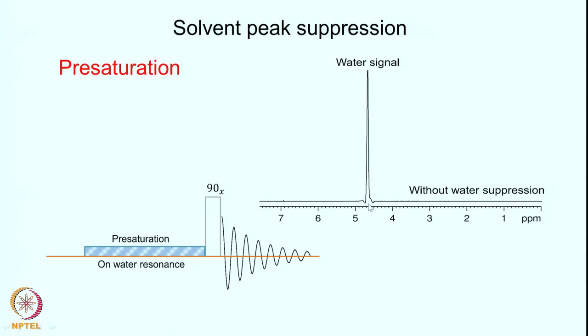Here is the spectrum of a sample in water. You have a huge water signal — this is a spectrum without water suppression, and you will see only the signal of the water; you do not see anything of your sample at all. One way to suppress the solvent signal is to do what is called a double resonance experiment, where you use a second RF and irradiate the solvent resonance. The second RF frequency matches exactly with the water resonance, so you put that RF here with reasonably high power, so that it only affects the energy levels corresponding to the water and all the other signals are not affected to a reasonable approximation.